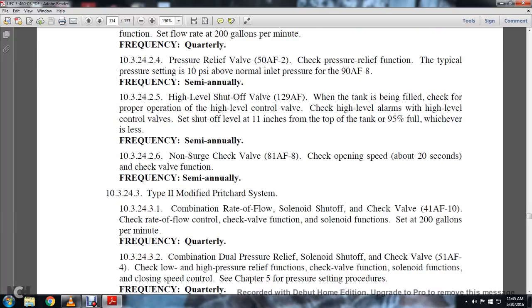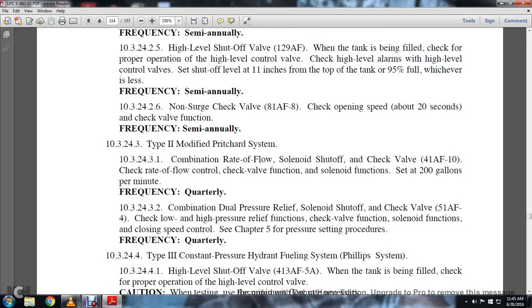Alright, moving on to a Type 2 modified Pritchard system. Combination rate of flow solenoid shutoff check valve: check rate of flow control, check valve function and solenoid function, set at 200 gallons per minute. Do that quarterly. Combination dual pressure solenoid shutoff check valve: check low and high pressure relief function, valve function, solenoid function, and closing speed control. See Chapter 5 for pressure setting procedures. Quarterly.